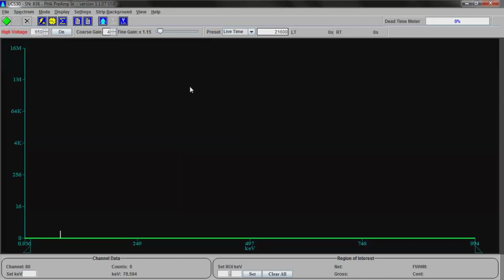By the way, live time versus real time. There are periods of time when the detector can't detect because it is down. It is waiting for the next time to be able to actually detect. This has to do with a lot of math and how often the detector is hit by gamma rays. But basically, live time is a count of how long the machine has been running when it's been able to detect something, versus real time, which is just how long the machine's been running. We always run for 6 hours of live time.